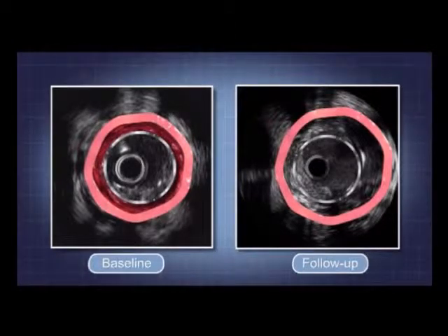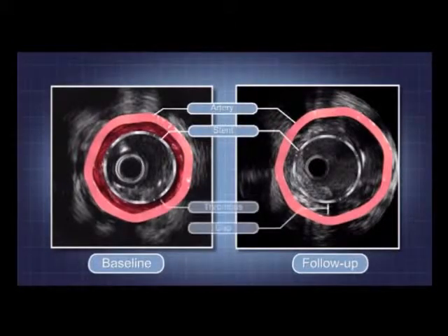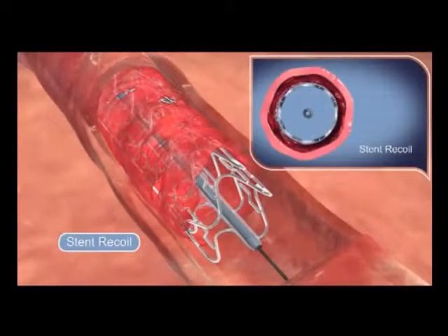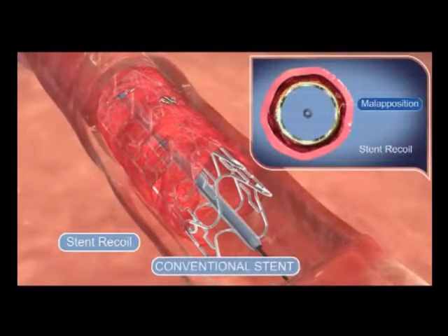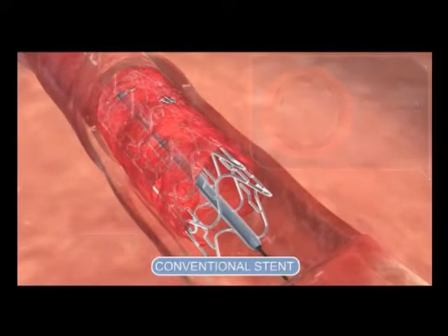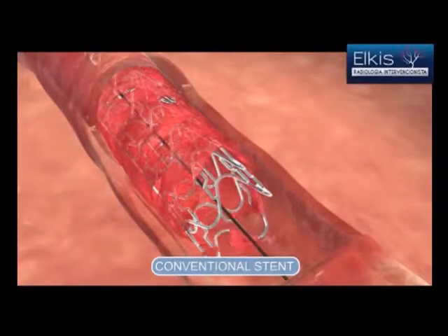how a stent which appears well deployed on the left-hand side resulted in a gap between the stent and the vessel wall after 13 months, as shown on the right-hand side. How could that possibly happen? First, as the balloon that delivers a conventional stent is deflated, the stent's natural tendency for recoil could result in initiating such a gap between stent struts and the vessel wall.